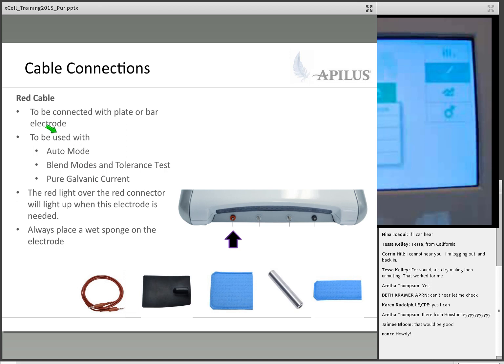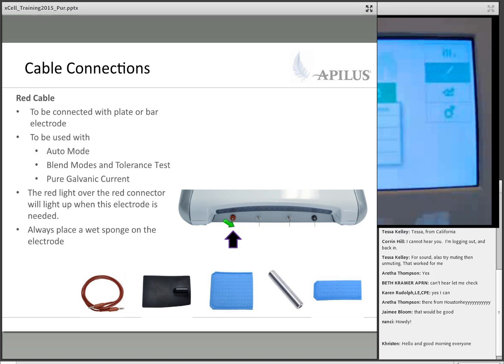We use the red connector for auto mode. We use the red connector for blend modes, the tolerance tests, and when we do pure galvanic. So anytime that direct current is used or some sort of feedback is needed, we are going to need the ground. The light right over the connector will turn on when this is necessary. So you'll actually have a little light that will shine directly on that cord, letting you know that the cord is actually required. So when you work auto mode, which is working without the foot pedal, when you engage auto mode, the light will light up on top of the red cord, and that tells you that you actually need to give the client the ground in order to be able to do auto mode. Always place a wet sponge on the electrode. It just is better for conductivity.